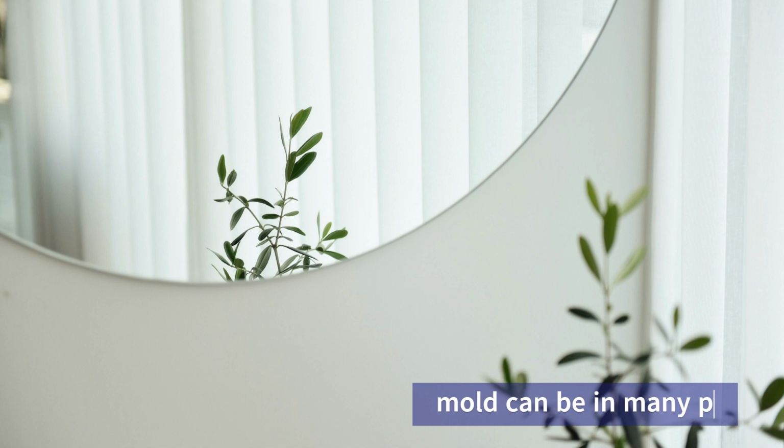We're looking to find out if the conditions in a home are conducive to the creation of mold. And so we're examining all of the potential areas of mold. For example, we're looking at whether or not your bathrooms are venting properly, whether your attic has proper insulation, whether the ductwork in your HVAC system may have mold in it, measuring moisture content in basement walls, the relative humidity in your home, things like that.